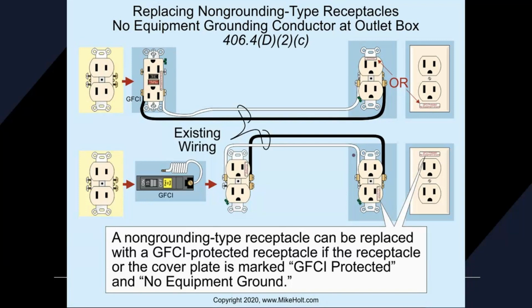Replacing non-grounding type receptacles, or no equipment grounding conductor at box. So here we go. You could put a GFI in as a breaker as well. You could put a GFI in the wall. Both have to be marked as no equipment ground.